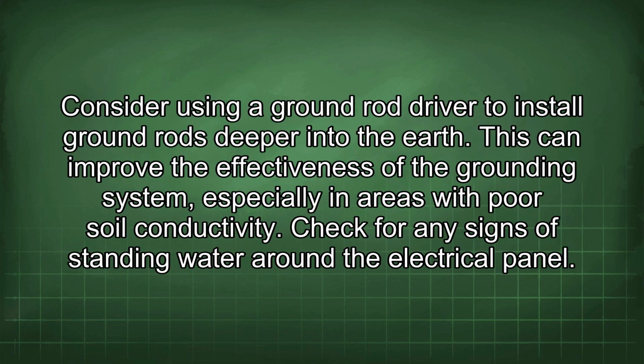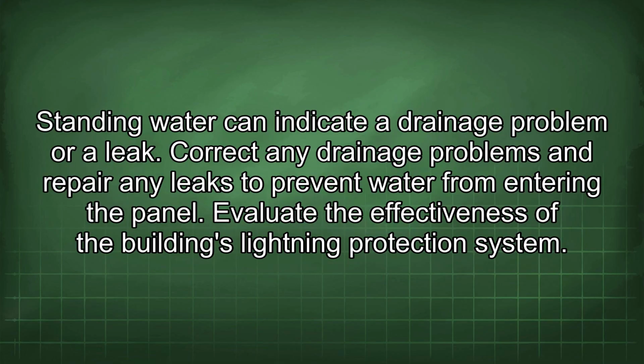Consider using a ground rod driver to install ground rods deeper into the earth. This can improve the effectiveness of the grounding system, especially in areas with poor soil conductivity. Check for any signs of standing water around the electrical panel. Standing water can indicate a drainage problem or a leak. Correct any drainage problems and repair any leaks to prevent water from entering the panel.